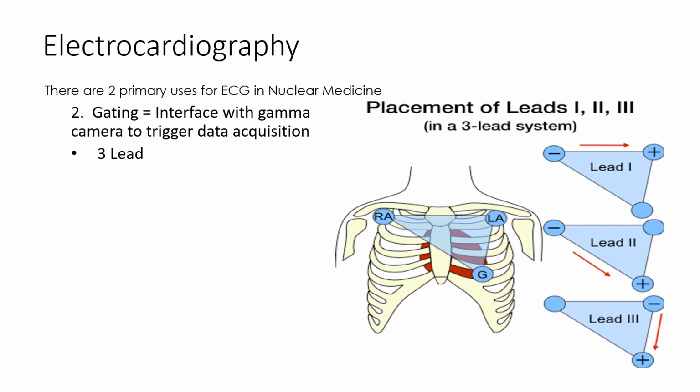It is important to place them in the right place so you're not getting a lot of interference. So right arm, left arm, and then the grounded one should go right here by the side. There are some newer cameras that require different gating. And so typically that will be on a sticker on the back of the scanner, and you would have some kind of training with that camera, particularly the solid state and multi-pinhole collimator cameras, especially like the one that GE puts out.